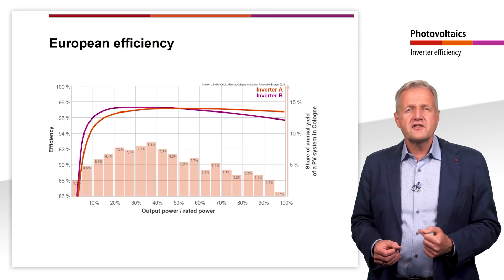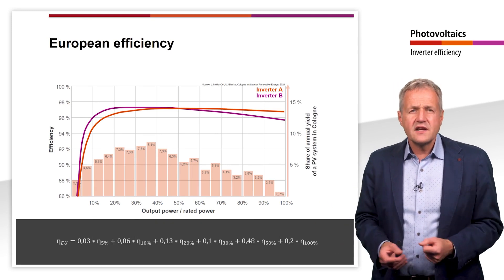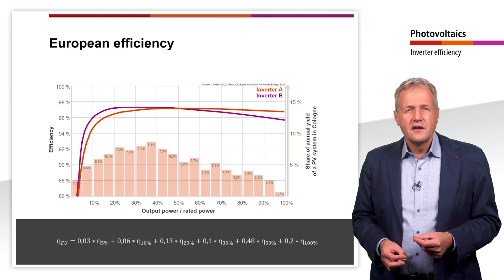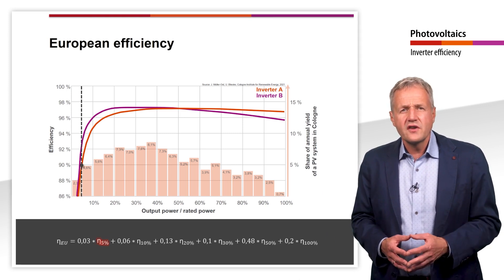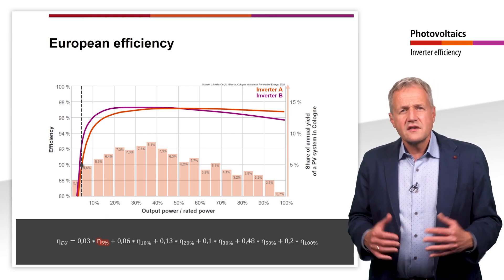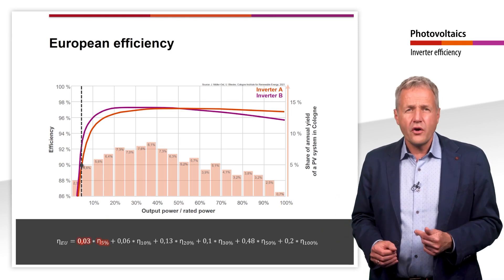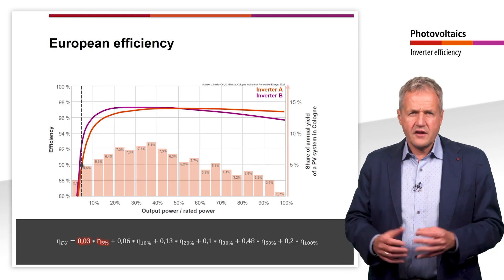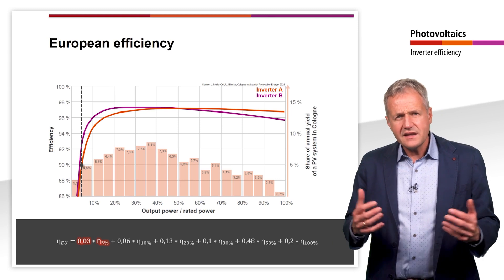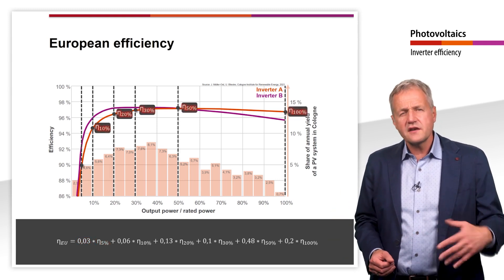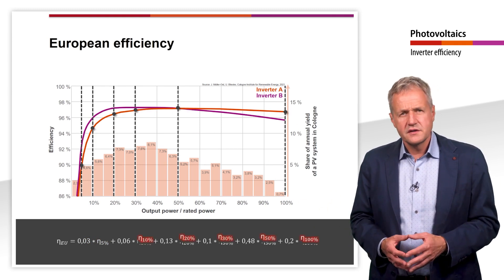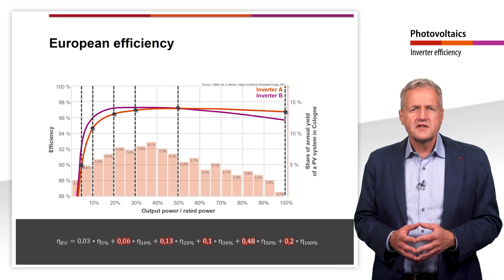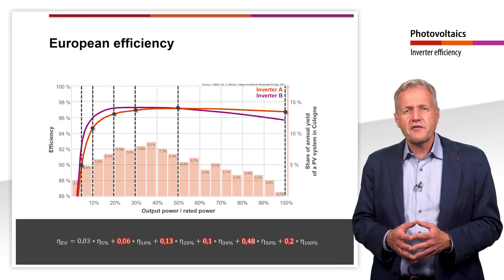For this reason, the European efficiency eta_EU was defined, which weighs the individual partial load efficiency according to the frequency of occurrence in Central Europe. The value eta 5% is the efficiency which occurs at 5% nominal power of the inverter. This efficiency is weighted with the factor 0.03 — so it is assumed that the inverter works 3% of the energy at 5% of the nominal power. Exactly the same is done with the efficiencies at 10, 20, 30, 50 and 100% of the nominal power, each weighted by a different factor. The highest weighting is given to the efficiency at half the nominal power, which is included in the calculation with a factor of 0.48.